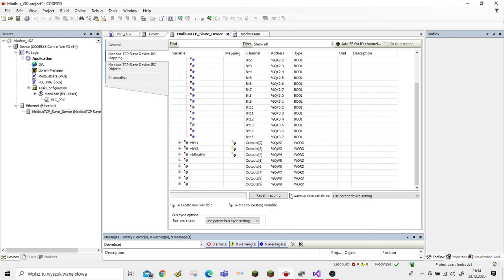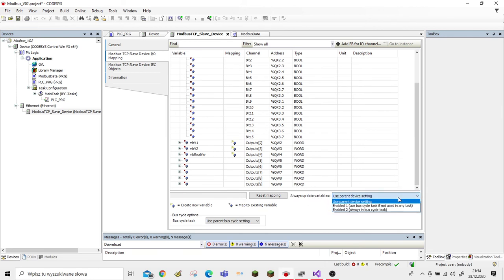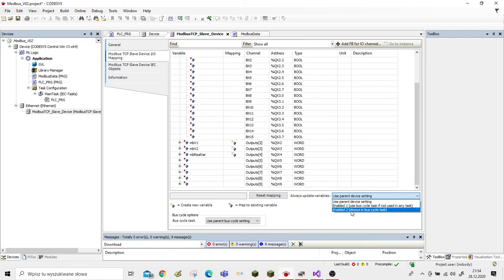To fix this, let's go to the Modbus TCP slave structure. We have to change the setting 'Always Update Variables' and choose 'Enable 1' or 'Enable 2' — we can use Enable 1. Let's write this to our project.